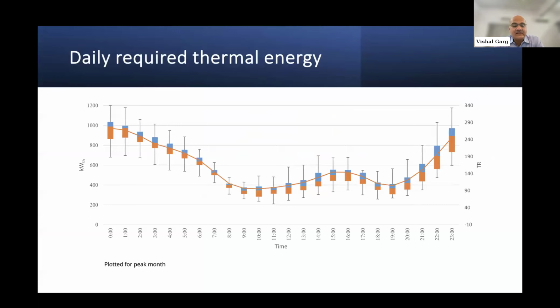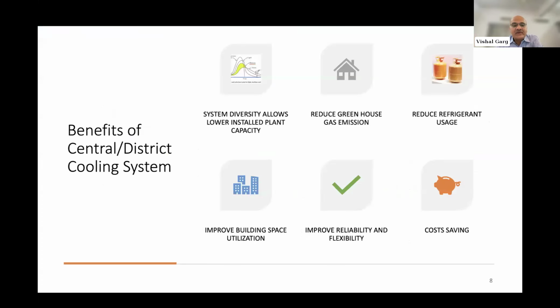Then we had collected data for this complex, and this is what we found as the daily requirement of thermal energy in the peak month. And here you can see the peak was around midnight, and it touched about 340 tons. And we have this data for 3 years, and it has never crossed 400 tons. So what is the benefit of district cooling in a residential space? It definitely leverages the diversity. So low installed capacity will suffice.